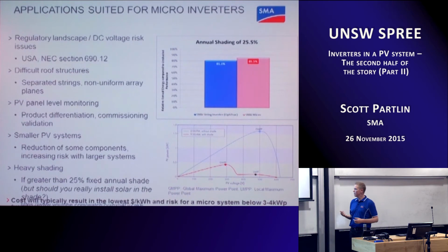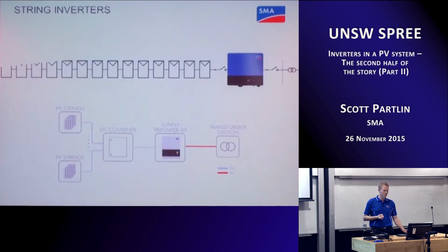And I guess just for the lowest dollar per kilowatt hour, once below about 4 kilowatts, a microinverter can often deliver the lowest cost for the system in terms of dollars per kilowatt hour. So if that's something that a consumer or whoever's installing the PV system is very interested in, then if that's their size range, this is where this technology or this inverter is best suited.